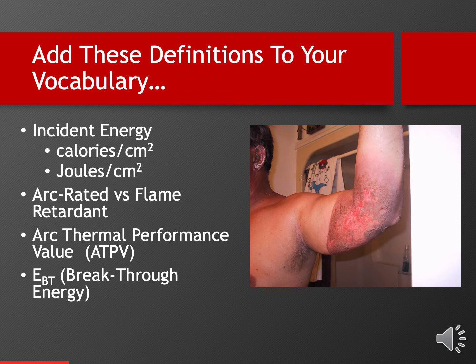So normally when we're talking about electrical safety on the job, we're going to be talking about using arc-rated clothing, not just flame retardant or flame resistant. Then you'll see the ATPV value, the arc thermal performance value. That is the same as an arc rating. So if you see that in the regulations, that's what it's referring to. And then, as I mentioned at the bottom, the E sub BT is breakthrough energy.